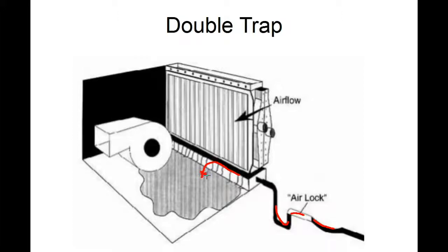If you are having condensation that's backing up into the air handling unit and you know that the trap is per manufacturer's specifications, it's time to start crawling the attic and looking for this bow or this double trap. This is what you're going to find in most instances is a double trap and usually a big bowed line over a long distance. Or it can be a line that is laying on the ground and then has just a little uprise at the top and that creates a double trap as well.